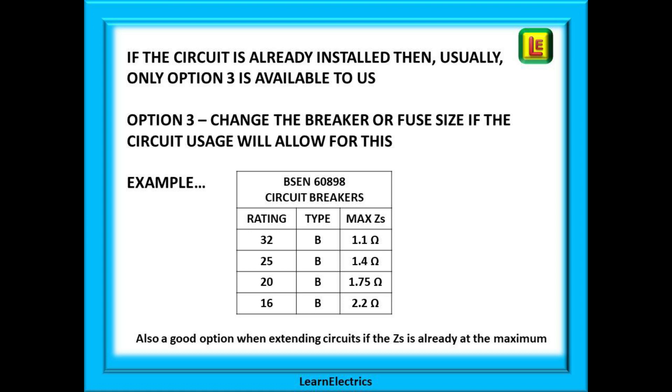This table shows some examples. This is also a good option when extending circuits. If the ZS is already at or near the maximum and you know that extending the cables will exceed the ZS requirements, installing a smaller breaker will increase the permitted ZS that you have available. Just like the seesaw, if we make the circuit breaker size lower then the permitted ZS will go higher. Imagine that we have just measured the ZS and it is 1.3 ohms. The table shows that this is too high for a 32 amp breaker. It has a maximum of 1.1 ohms. But we could change the 32 amp breaker for a 25 amp breaker that has a maximum ZS of 1.4 ohms. 1.4 ohms maximum is more than 1.3 ohms measured, so this circuit will be safe.